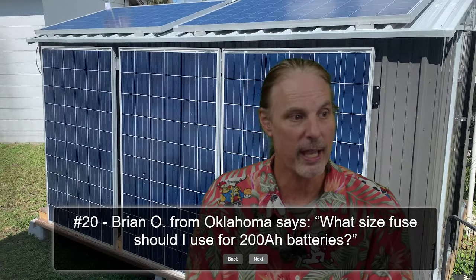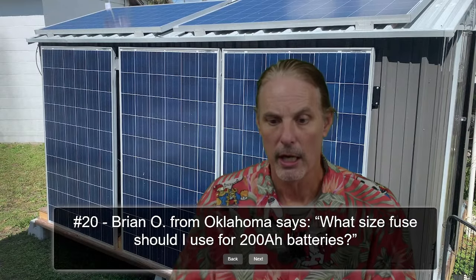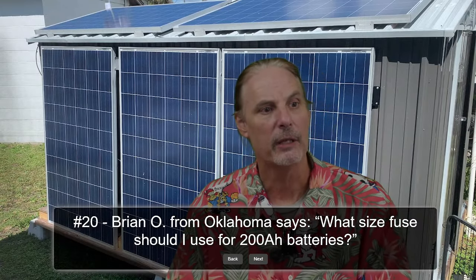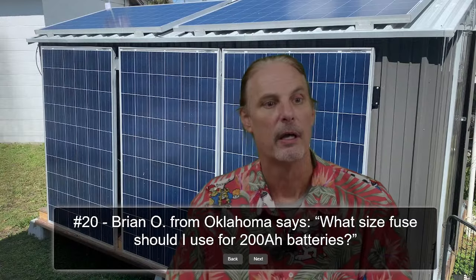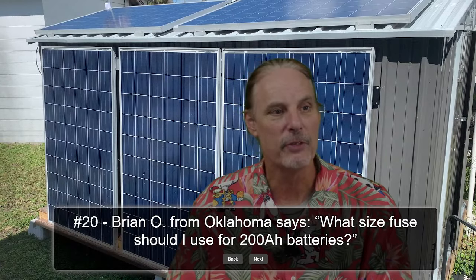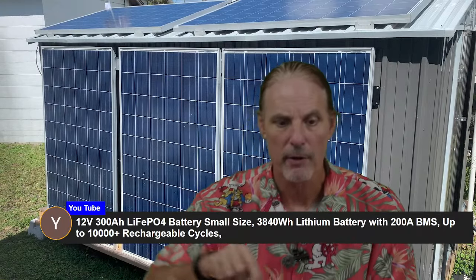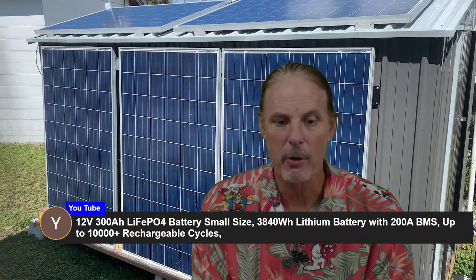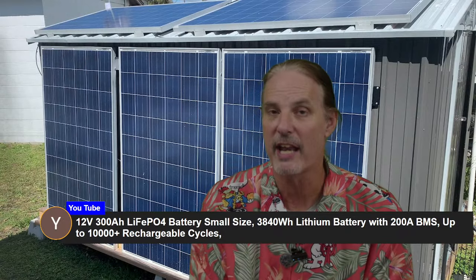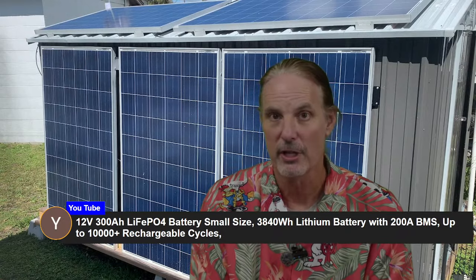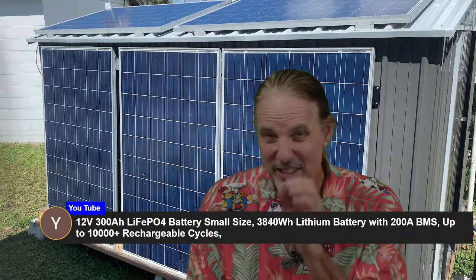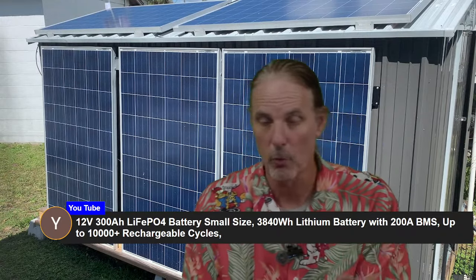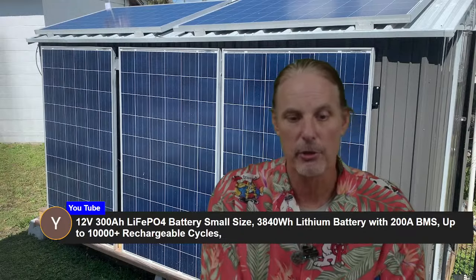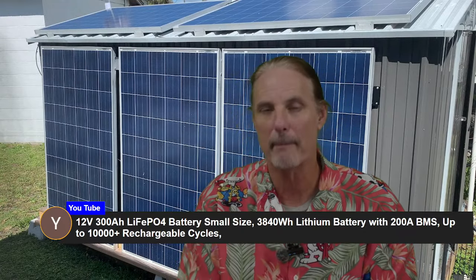If it's a 100 amp hour battery like it was with, and I want to go back to the previous question and kind of show this, and I'm going to have to turn this one off. So in this case, you have a 300 amp hour battery, but he also specified that it had a 200 amp BMS. And so not always in the case do these match one for one. Usually if you have a 100 amp hour battery, you also have a 100 amp BMS.